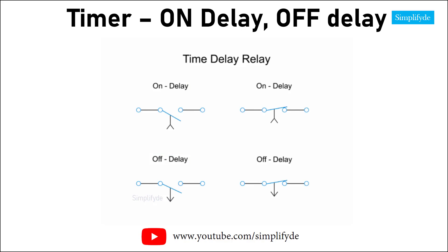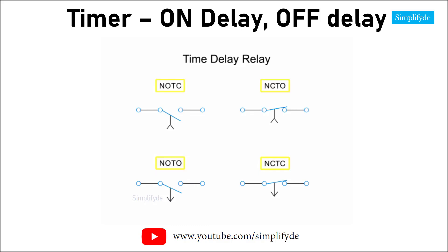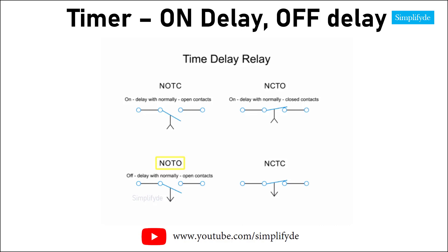Let's look at four basic types of relays. There are two types of relay functions: on delay and off delay, each with two types of contacts — normally open and normally closed — represented here by four symbols. NOTC functions as an on delay with normally open contacts. NCTO operates as an on delay with normally closed contacts. NOTO functions as an off delay with normally open contacts, and NCTC operates as an off delay with normally closed contacts.